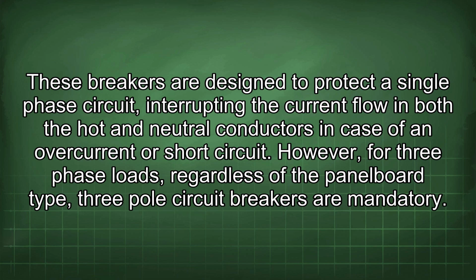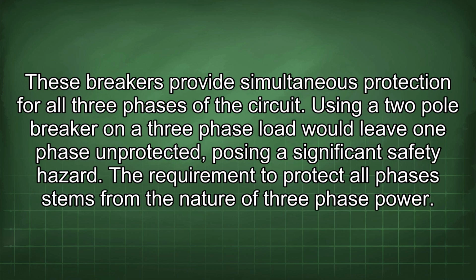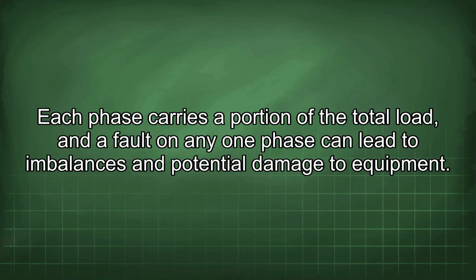However, for 3-phase loads, regardless of the panel board type, 3-pole circuit breakers are mandatory. These breakers provide simultaneous protection for all 3 phases of the circuit. Using a 2-pole breaker on a 3-phase load would leave one phase unprotected, posing a significant safety hazard. The requirement to protect all phases stems from the nature of 3-phase power. Each phase carries a portion of the total load, and a fault on any one phase can lead to imbalances and potential damage to equipment.